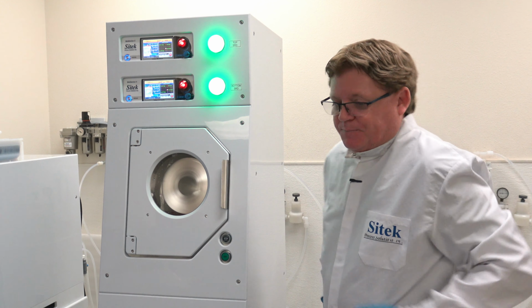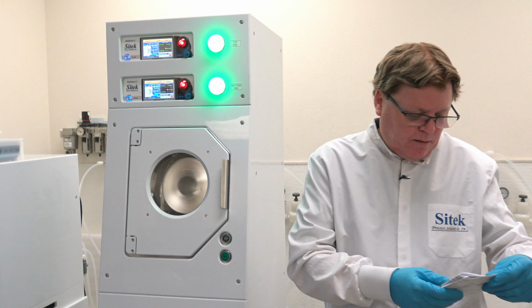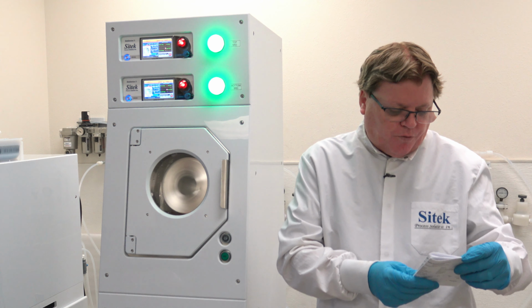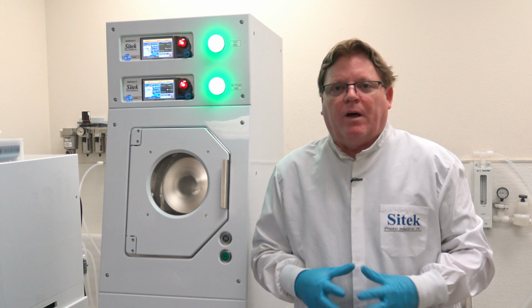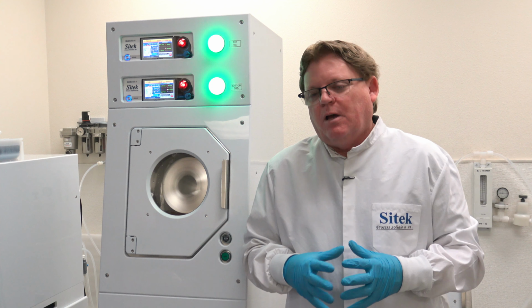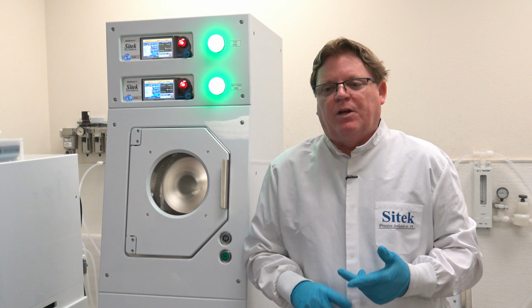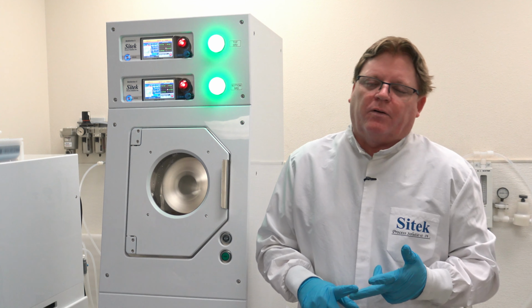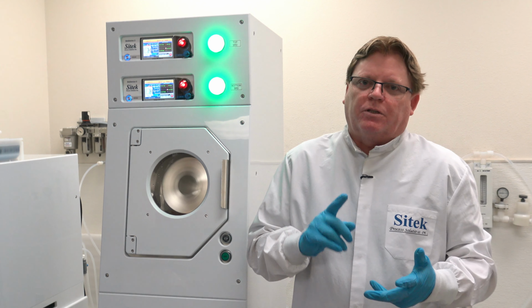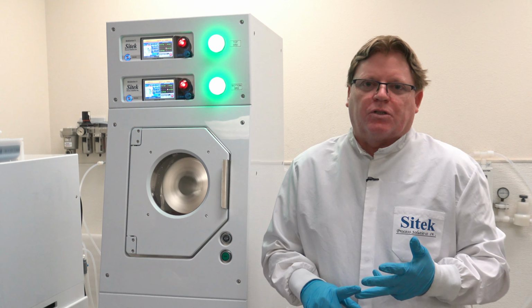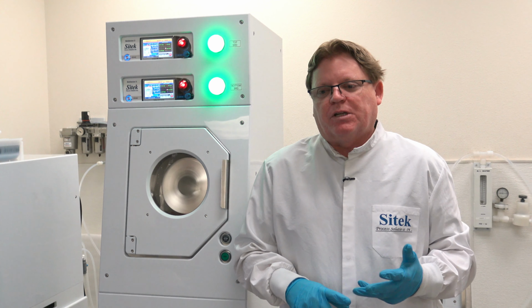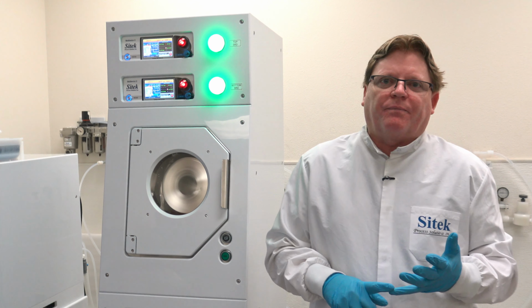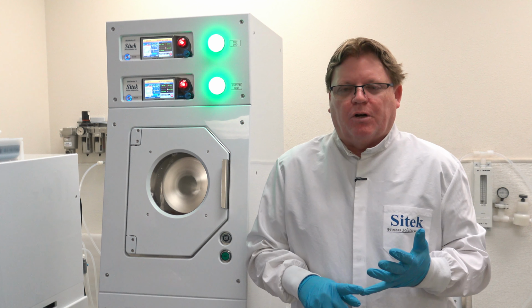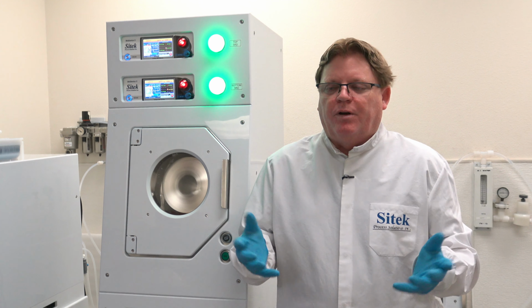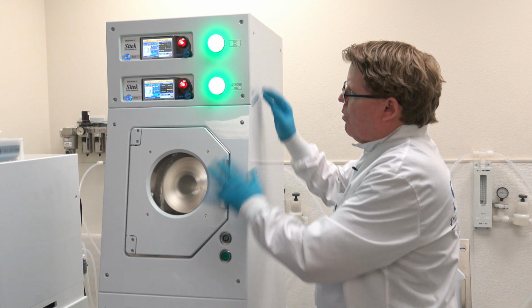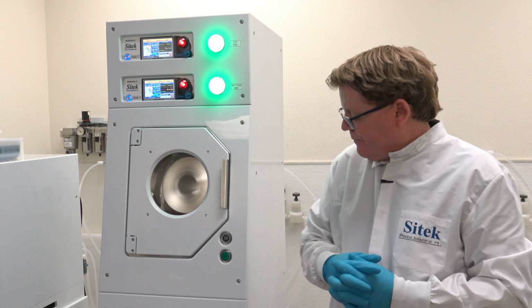This system, if I remember correctly, is fully refurbished. We go ahead and do the refurbishment of all the valves. We replace all the Teflon tubing, brand new, all brand new pneumatic colored tubing. We go through and change out the sensors, that would be the N2 pressure sensors. We do new rotor stop positioners, new heater blankets. In fact, everything on this system, 100% we offer as new parts.